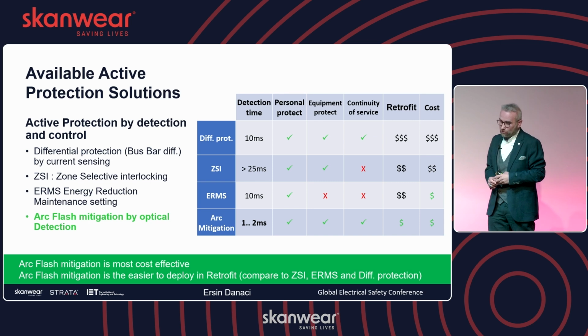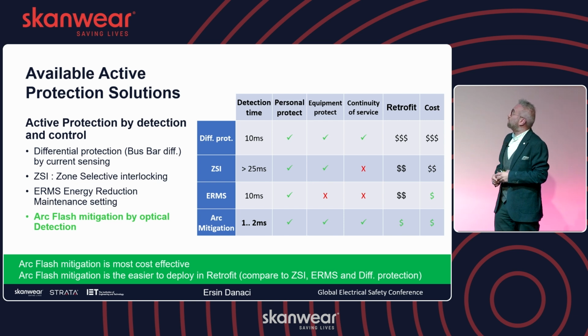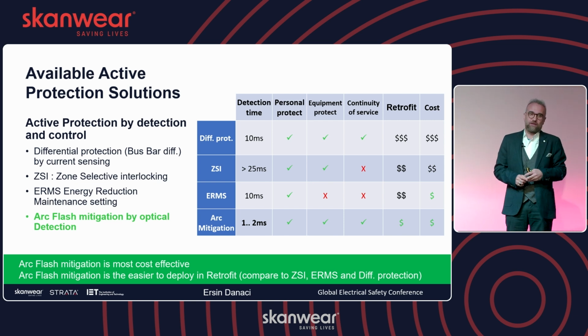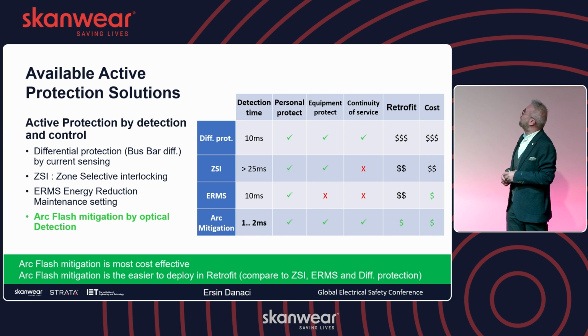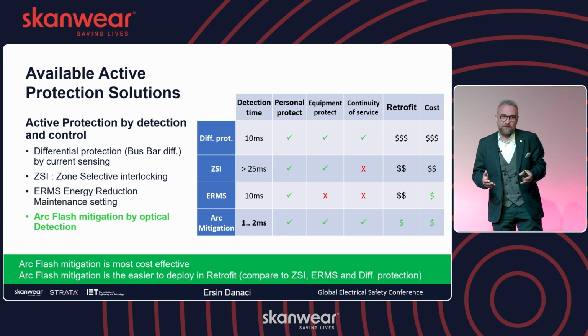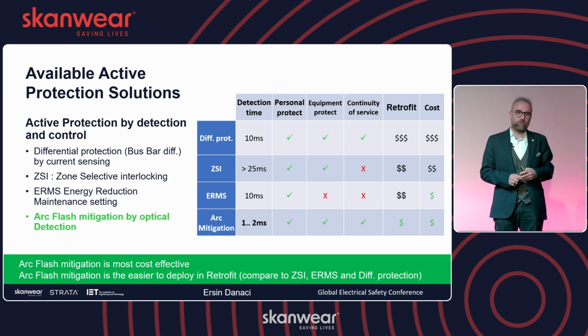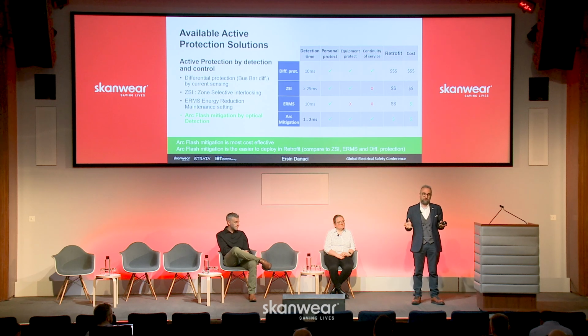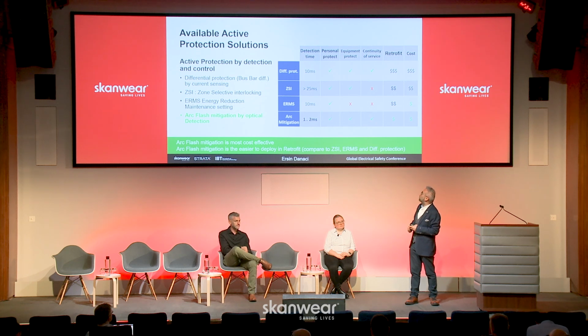On this slide you can see various options and solutions for mitigation: differential protections, ZSI, ERMS, and arc mitigations with arc technologies. There's different reaction and response times from the products. Time is very crucial, because we have to clear the fault and the explosion as quickly as possible. As you can see from the chart, arc flash technology has quicker response and detection - 1 to 2 milliseconds.